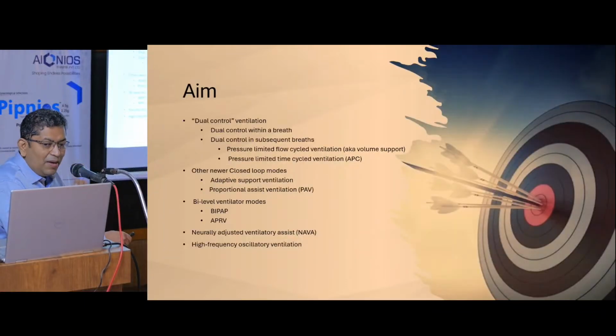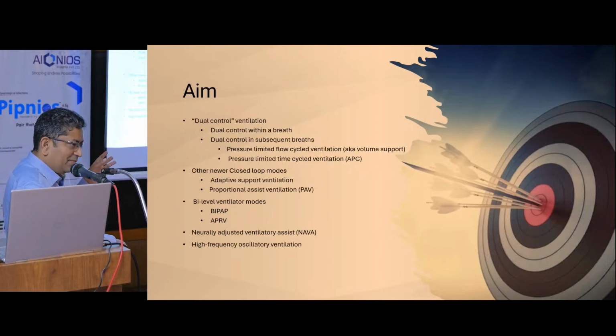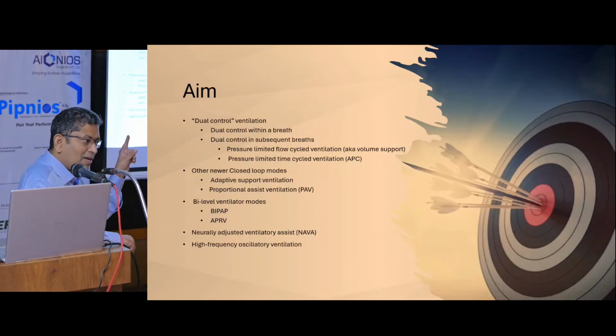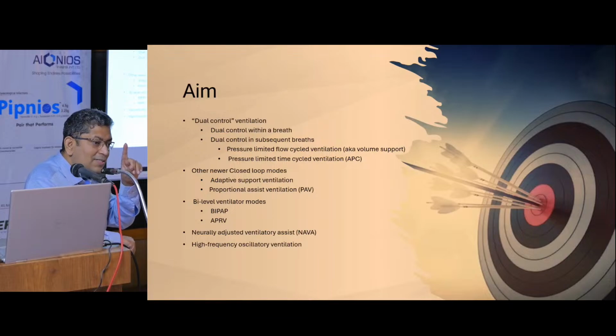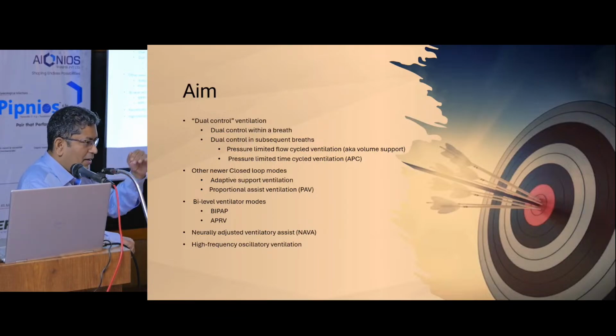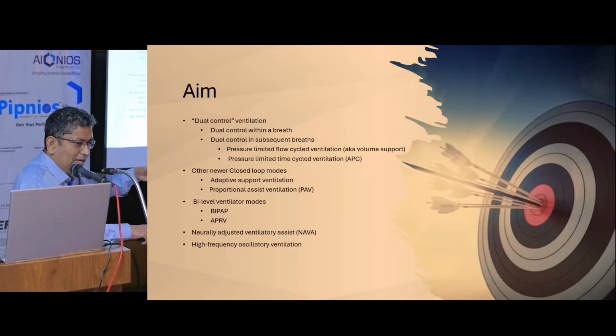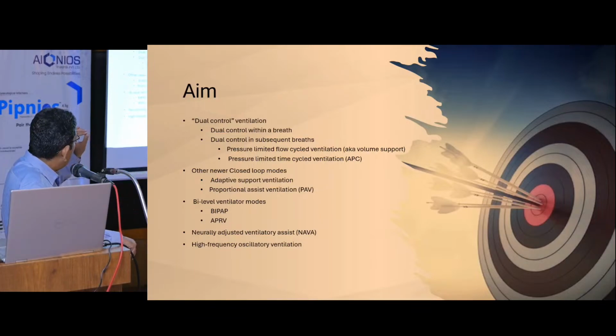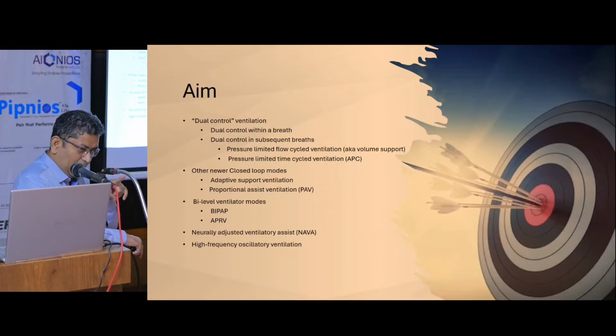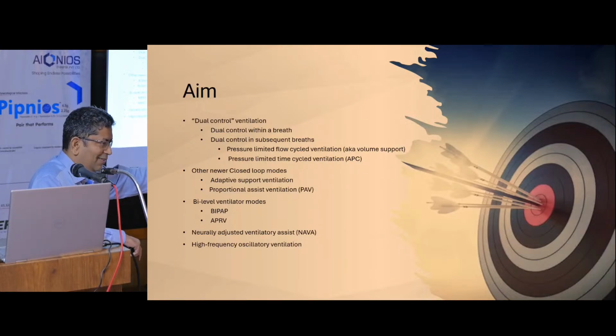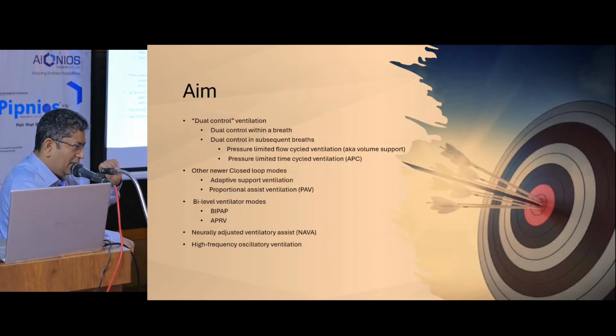All right. So the aim now is to understand dual control ventilation. Till now, it's all been single control, a single set point. Now we have two set points, which will change things. You can have dual control within one single breath. Normally pressure control is always pressure control, but then suddenly it goes from pressure control to volume control in one breath. So that's dual control in one breath.